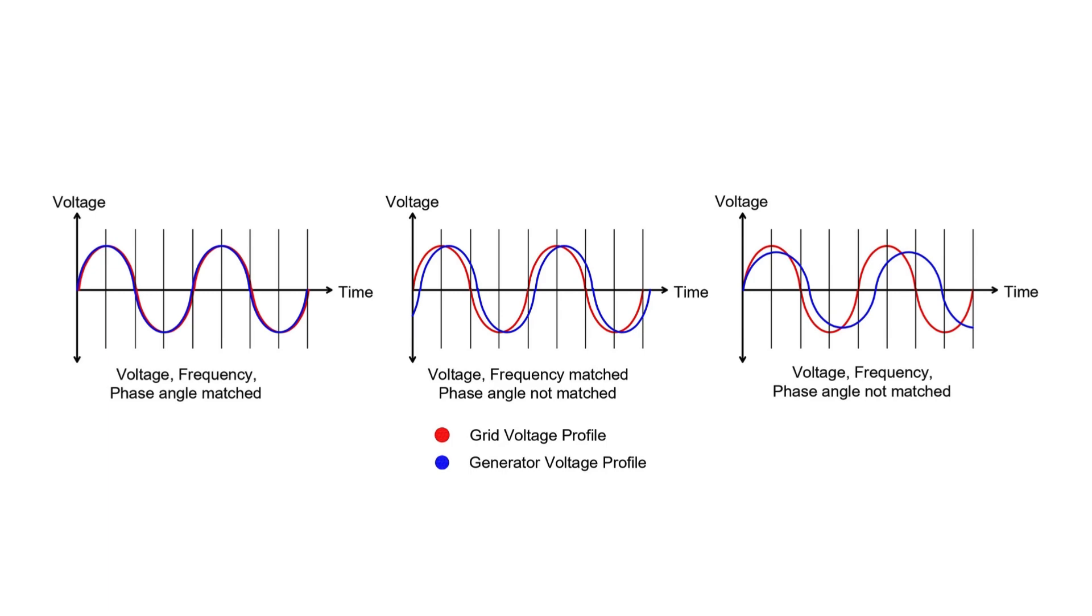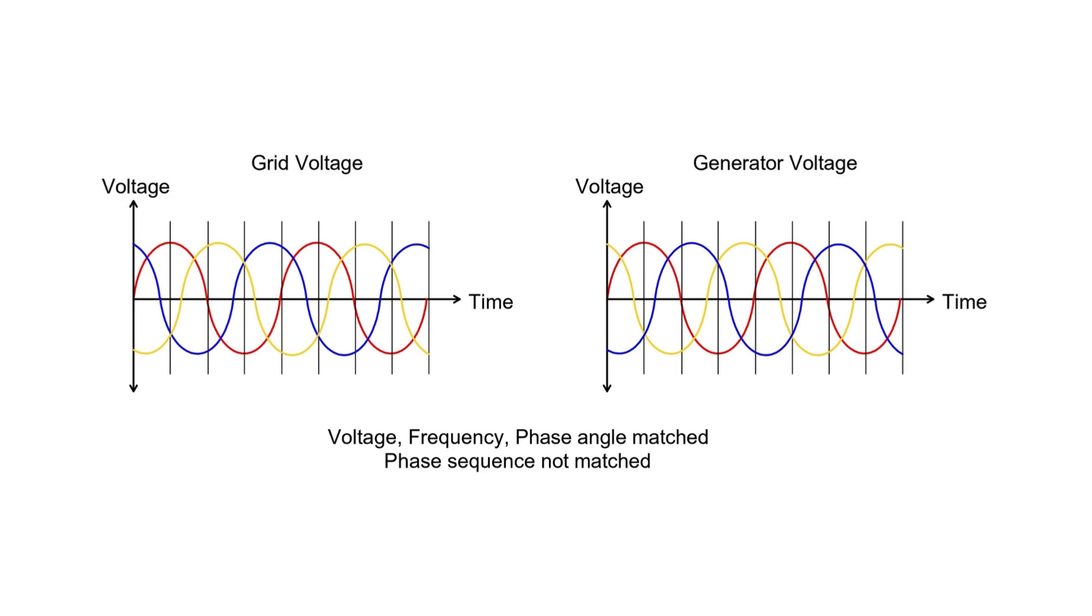Since the voltage produced by the alternator is AC, the voltage profile of the incoming generator must match the running generators, requiring similar parameters. If the voltage profile doesn't match when the breaker is closed, the voltage difference could damage the generator.